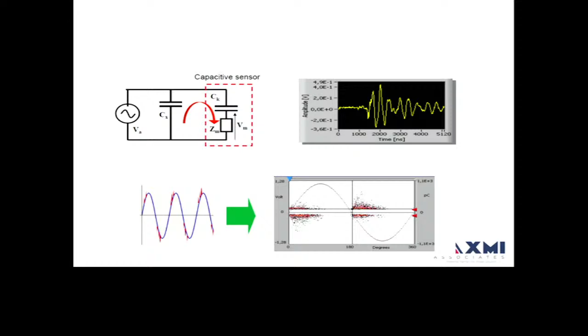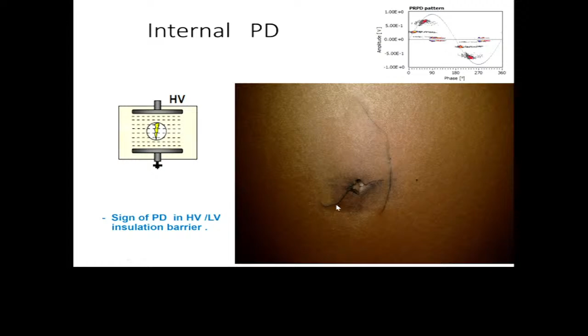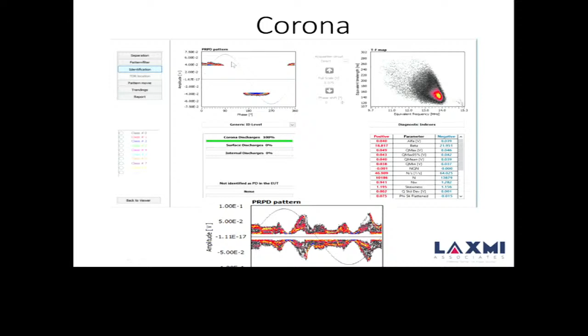So I'm skipping this introduction, going directly to the case study. Suppose you have a partial discharge, you will get a clear PRPD like that, and it shows internal discharge. What you are seeing is a cluster here, that shows an internal discharge. In the photograph, this is a real internal discharge on the pressboard, which was captured, and after inspection it was found. This is a corona. You can get that.